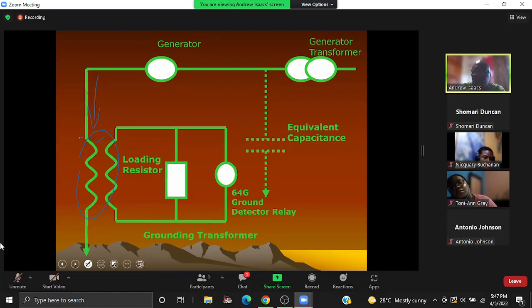Based on the voltage on this side, let's start. On this side, we know that the voltage on the secondary is between 100 and 500. In the scheme of things, that is low, right? So if you have low voltage on this side, it means that you're going to have a higher current over here. And that high current will give us a voltage across this, which will then operate our relay.